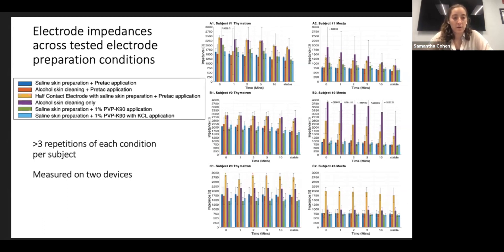Then we had alcohol skin cleaning only with no conductive gel. And then we prepared our own solution to mimic the role of Pre-Tac, which was used with a polymer PVPK90, and we had two conditions, one with just PVPK90 and one with KCL, which is just a salt. And those were both prepared with saline skin preparation. So for each subject, there were at least three trials for each condition, and this is accounted for in the error bar seen on the graph. Two commercial ECT machines were used to measure static impedance, the Thymatron and the MECTA.